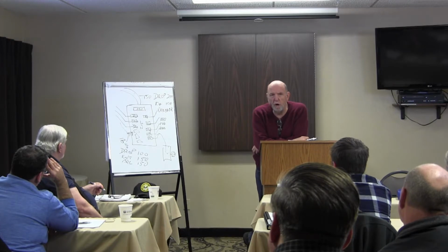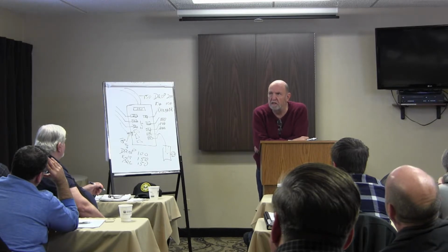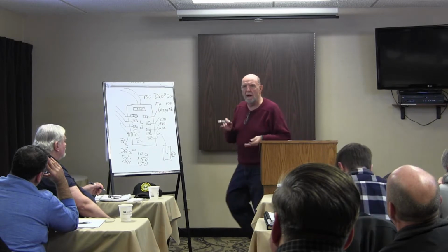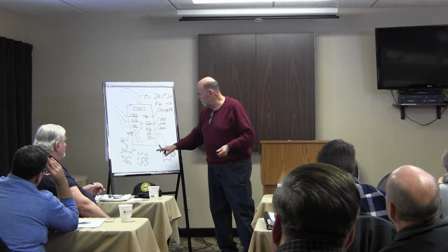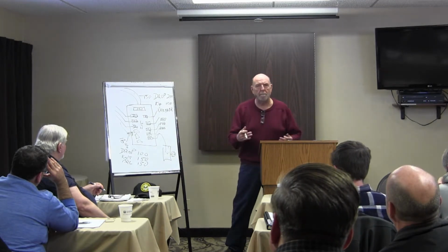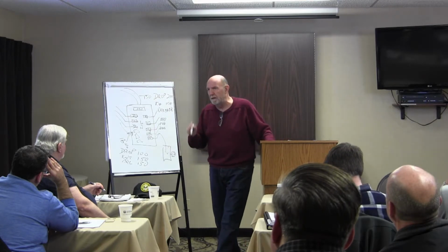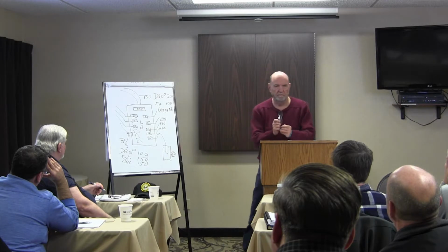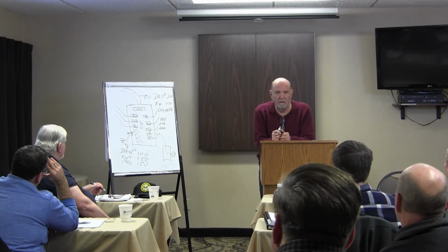No, the wire was just fine, because the service size is defined by the smallest. The breaker size is wrong. On top of that, it's just less expensive to change the breaker than to run new wire. Okay?